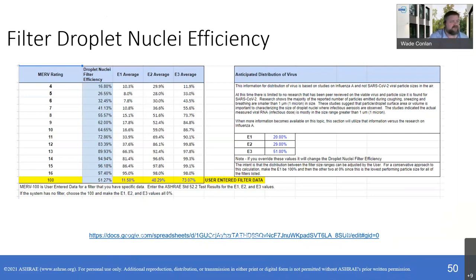That is a single point value that you can say, if I multiply that by the amount of recirculated air, not total air, just the recirculated air, because the outdoor air is clean, then I can say, okay, this is how much contaminant, here's how much clean air I'm going to have from this filter, depending on what I have. And then you say, wait, there's a yellow line and there's 100, right? It's a pivot table to look up. It has to be numerically in order. And so I tried to use the craziest number that I could, and I went with 100 just to try not to confuse anyone. For your situation, if you have your specific filters, which is very important to select the right filter, pleats per inch, et cetera, the pressure drops, the higher MERV doesn't always mean higher pressure drop. You can get stuff that's close. But then you can actually put in your own filter performance for your system instead of an average.